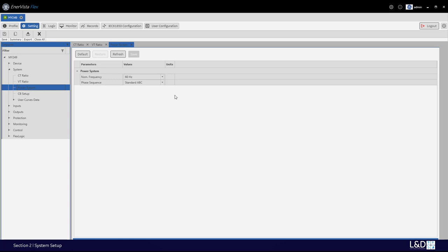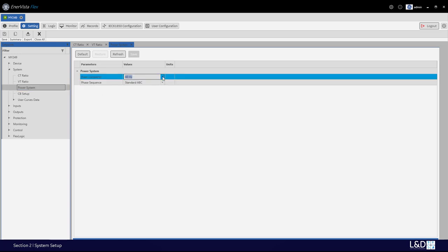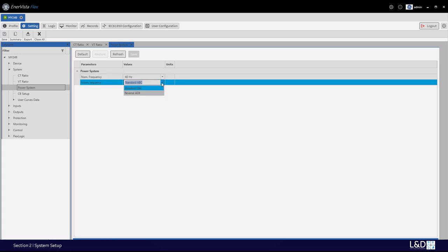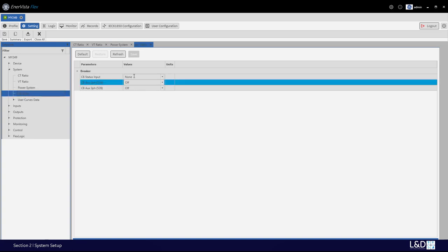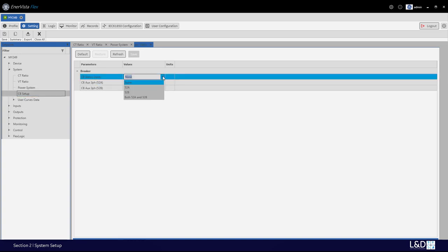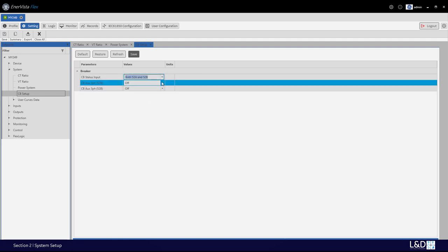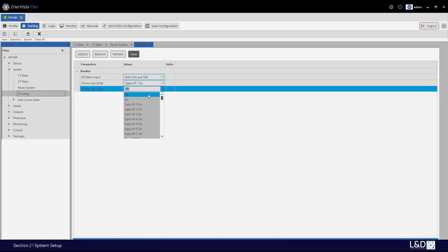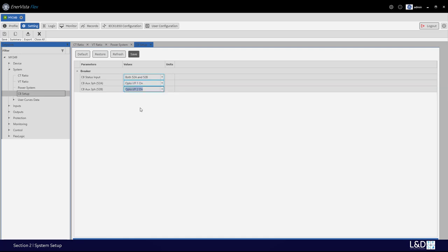Under power system, we can set the nominal frequency to 50 or 60 Hz. When valid frequency tracking is not available, this nominal frequency is used as the default to set the digital sample rate. The phase rotation can be set to standard ABC or reverse ACB. For the CB setup, we can set the status input to be 52A only, 52B only, or both 52A and B. If you set both, make sure the two status inputs are always opposite — input 1 and input 2 — otherwise you'll get an invalid CB status target message.